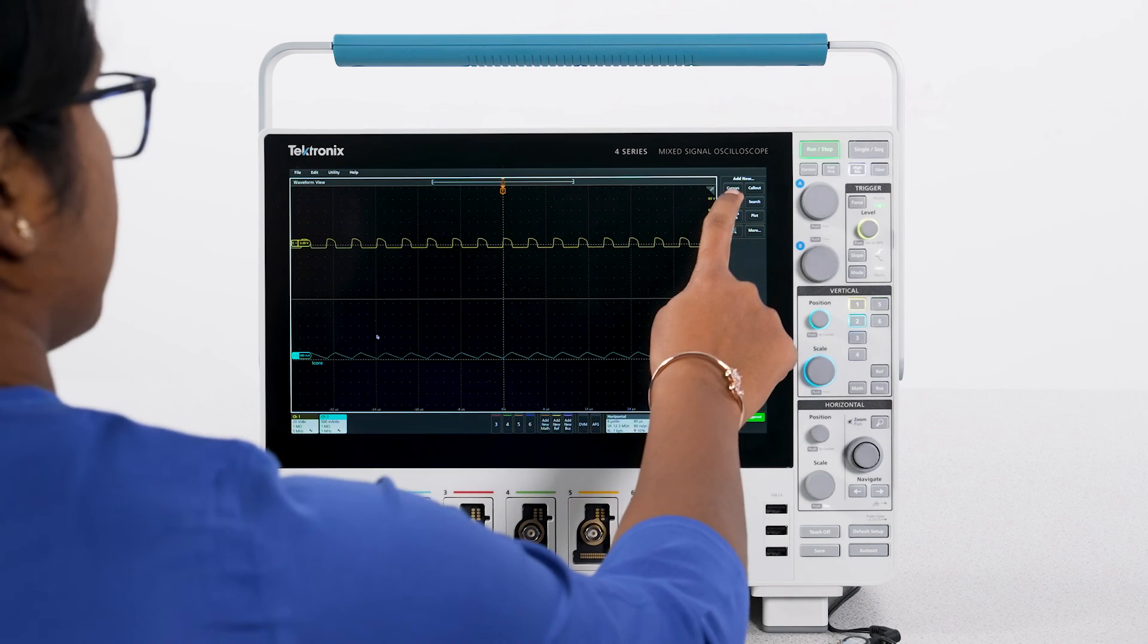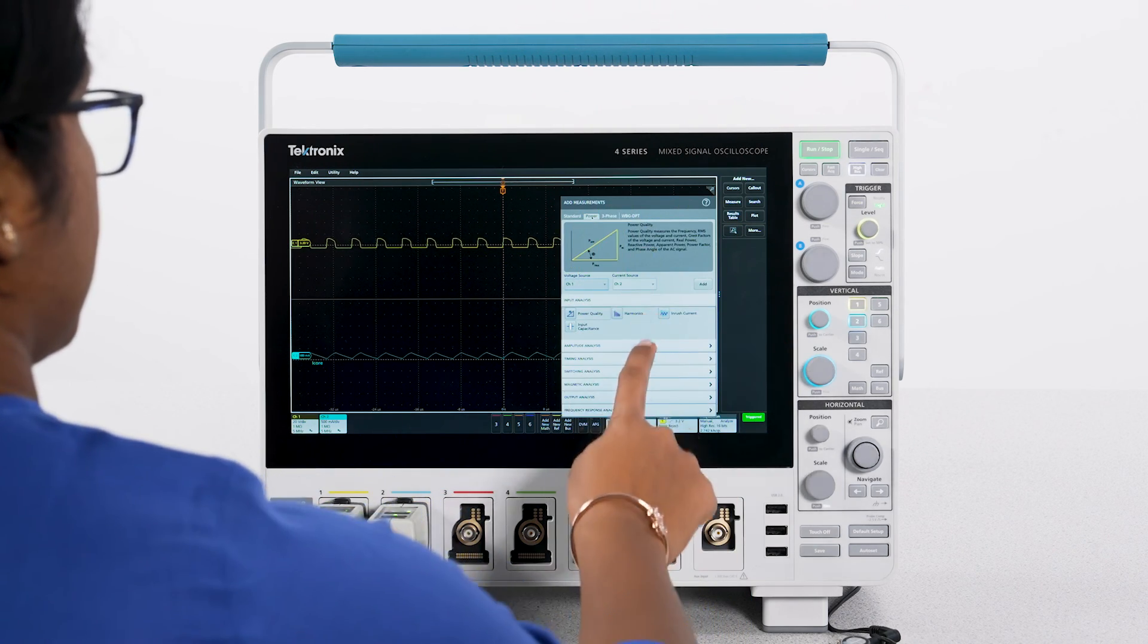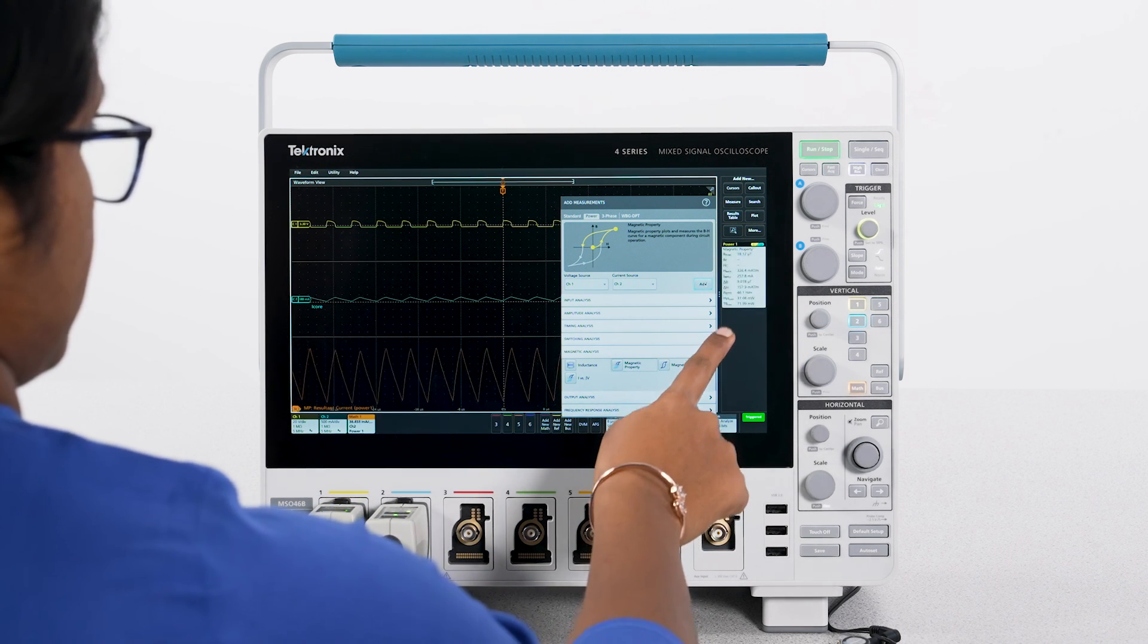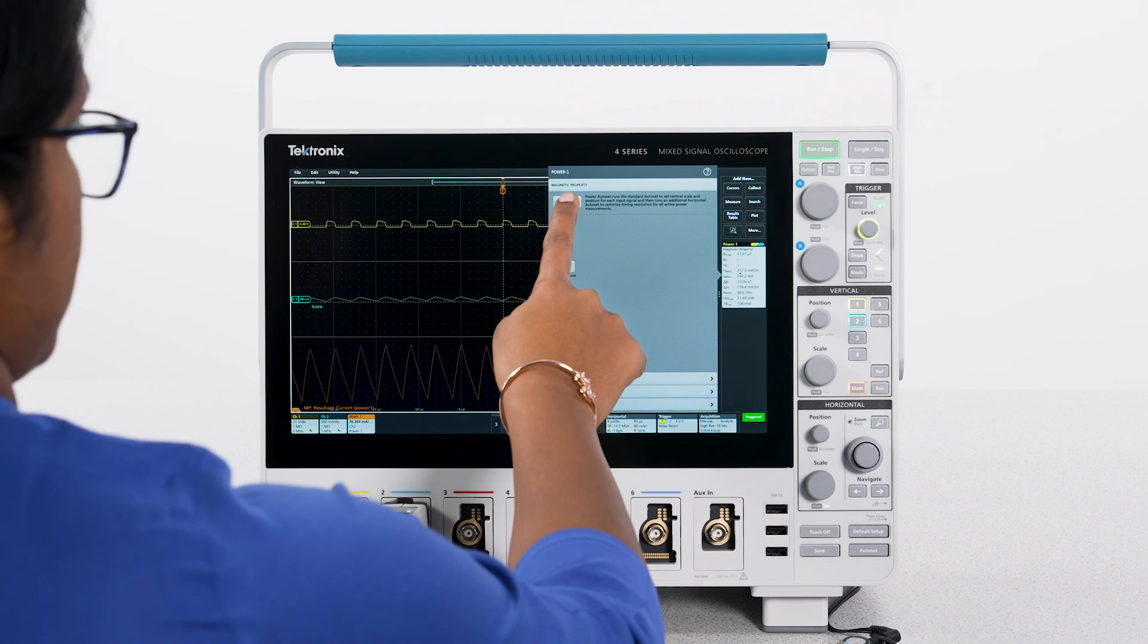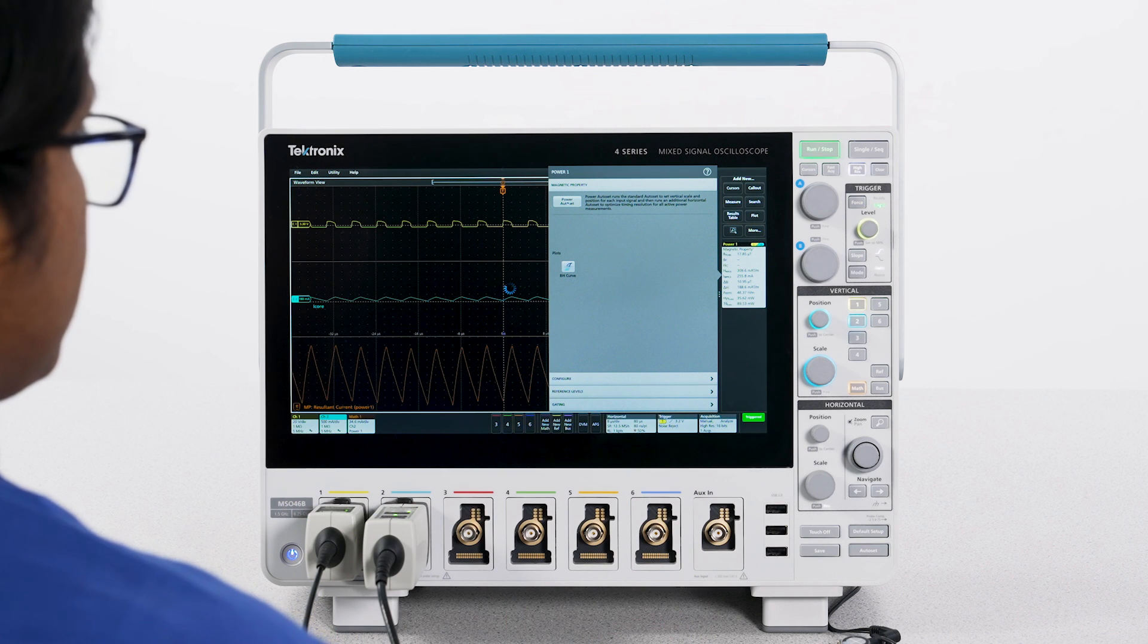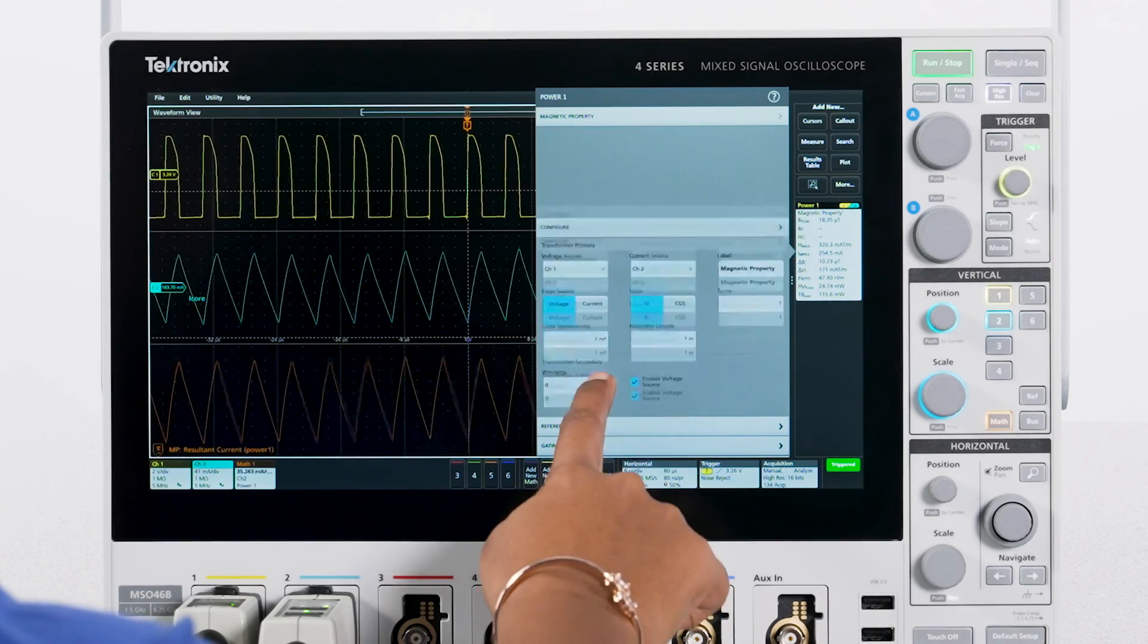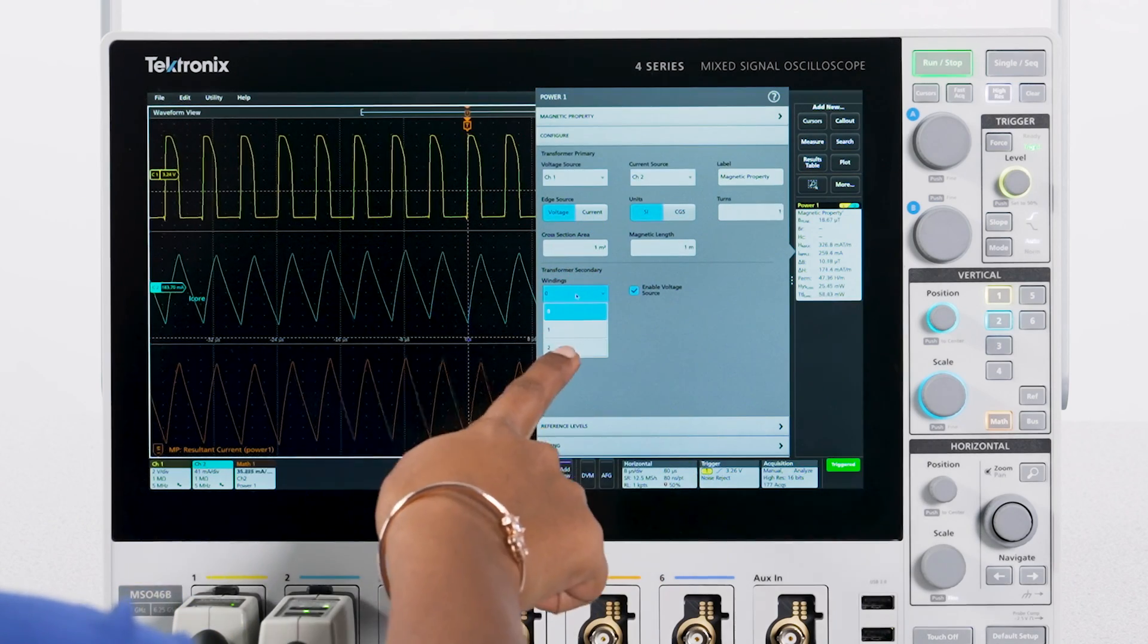The magnetic property measurement uses voltage and current to compute magnetic flux density, magnetic field intensity strength, and various loss components including hysteresis loss and total loss. The measurement also supports multiple transformer secondaries based on the scope channel count.